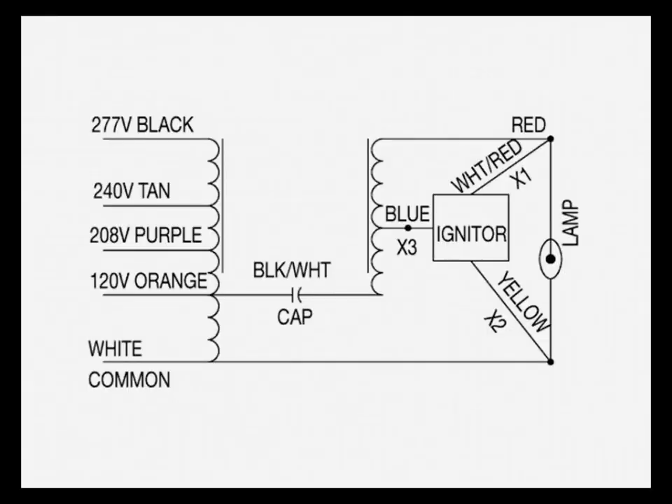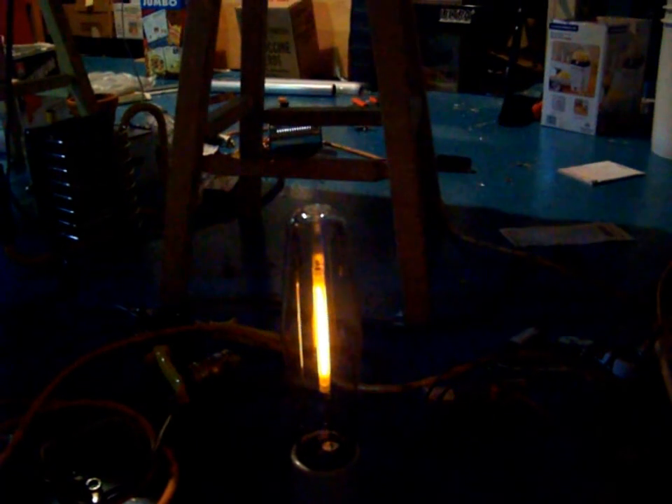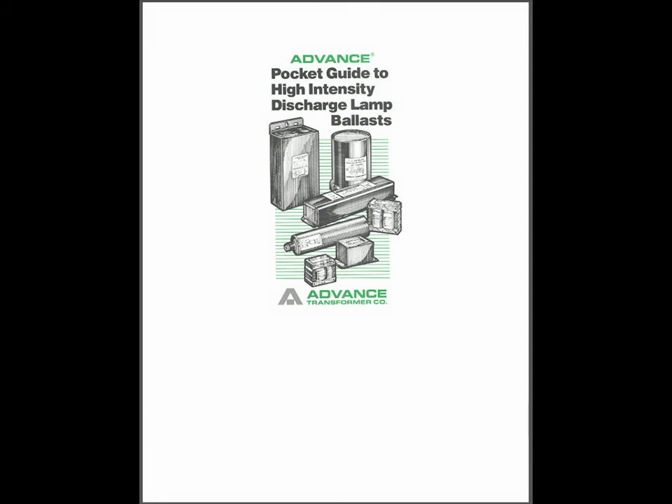As with a fluorescent starter, when the lamp ignites, it shorts the igniter and disables it automatically. And if the lamp shuts off with the ballast still being on, the igniter will constantly try to reignite the lamp. This may cause a premature failure of the igniter if a spent lamp is left in the fixture for too long. For further information, you can go on the Advance website and look for the troubleshooting documentation.